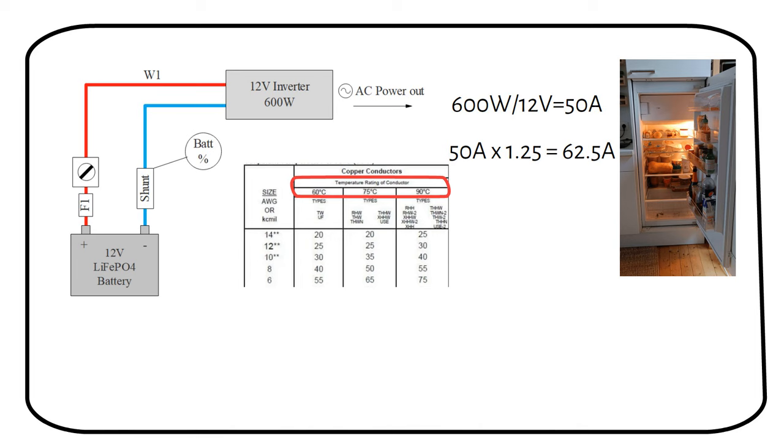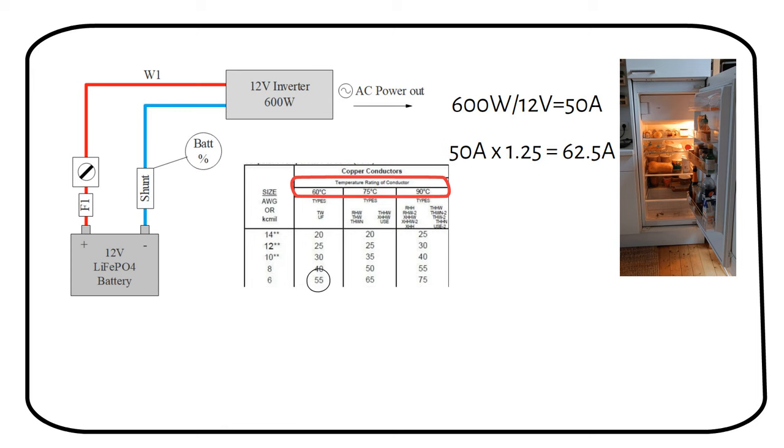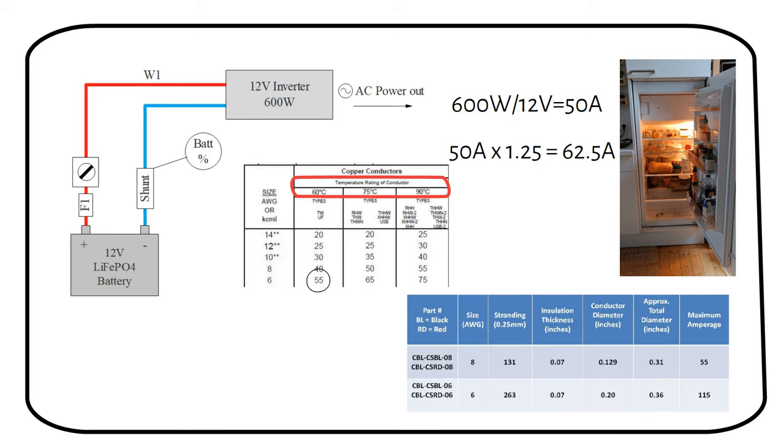For example, a 6 gauge TW wire, rated for 60 degrees Celsius, can carry a maximum of 55 amps. While a 6 gauge welding wire, rated for 105 degrees Celsius, can carry 115 amps. The main reason is the type of insulating jacket around the wire.